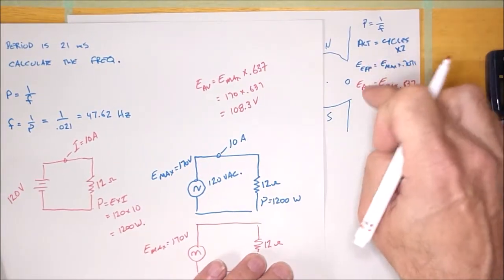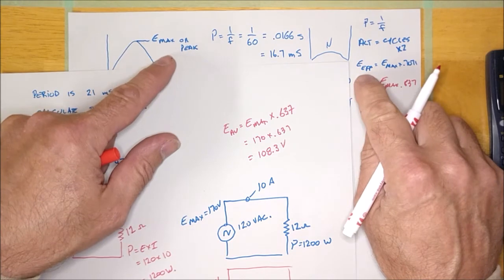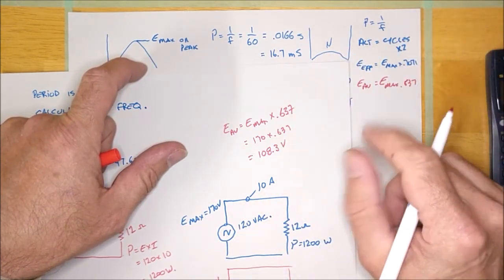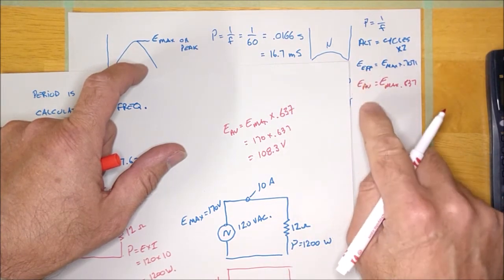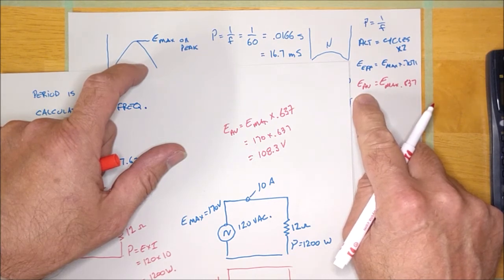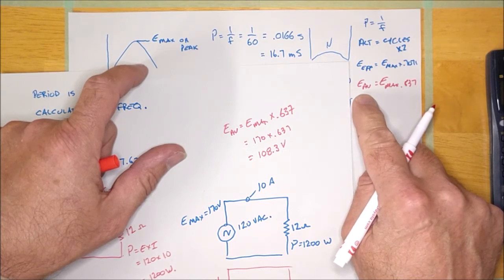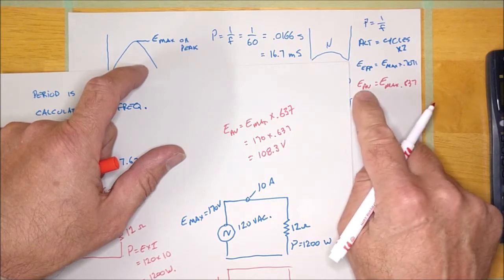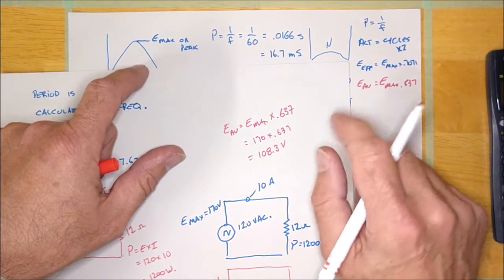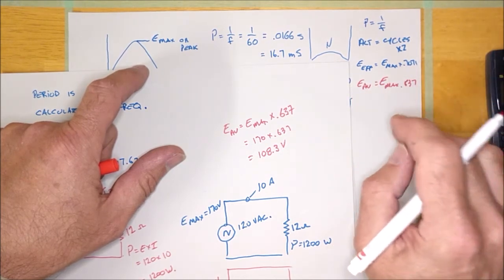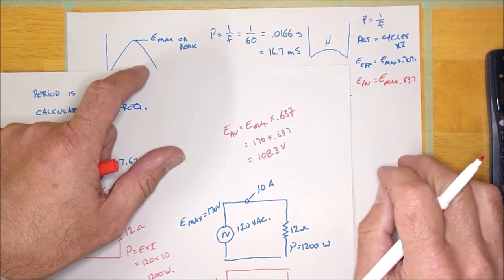So just to review these two formulas: peak and max are the same. Effective, RMS, and just straight up AC are all the same. If I say the effective voltage is 120, the RMS voltage is 120, or just the voltage is 120, we're talking about effective. Now, if I say the DC voltage is 108 or 200 or any other value, I'm talking about the average voltage. If you see average voltage, it means someone's done some rectification, because there's no such thing as the average AC voltage — it is the DC voltage. If you put your meter on DC, it measures average; if you put it on AC, it measures effective.